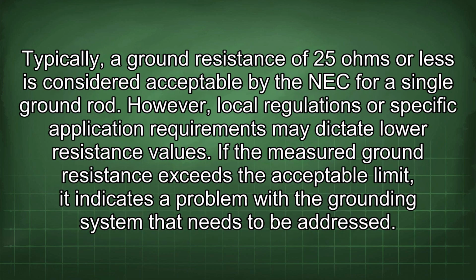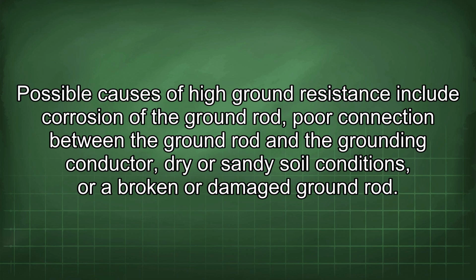Typically, a ground resistance of 25 ohms or less is considered acceptable by the NEC for a single ground rod. However, local regulations or specific application requirements may dictate lower resistance values. If the measured ground resistance exceeds the acceptable limit, it indicates a problem with the grounding system that needs to be addressed. Possible causes of high ground resistance include corrosion of the ground rod, poor connection between the ground rod and the grounding conductor, dry or sandy soil conditions, or a broken or damaged ground rod.